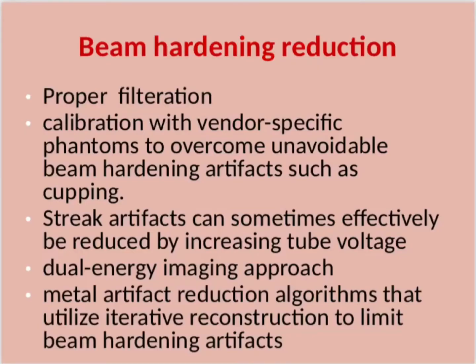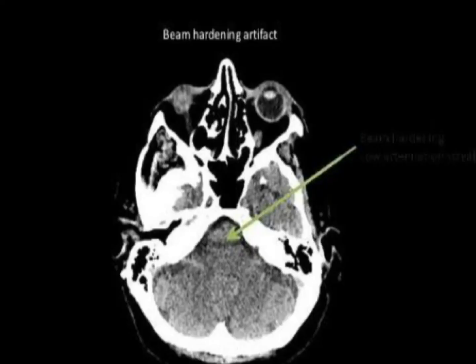Beam hardening reduction involves proper filtration and calibration with vendor-specific phantoms. To overcome unavoidable beam hardening artifacts such as cupping and streak artifacts, increasing tube voltage can sometimes be effective. Other approaches include dual energy imaging and metal artifact reduction algorithms that utilize iterative reconstruction to limit beam hardening artifacts.